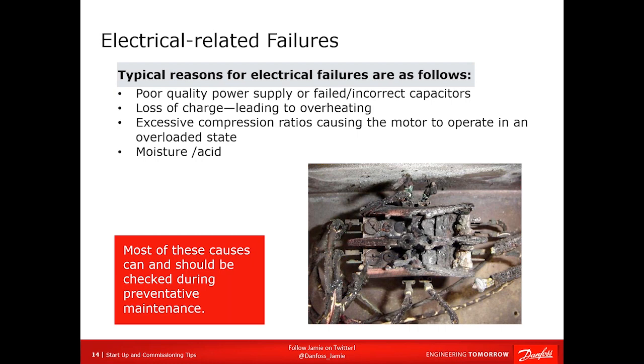All right, excessive compression ratios. We're going to look at the operating profile for these compressors. So if your compressor is operating in a set of conditions it's not designed for, and you overload the motor and not cool it, you're going to have an issue. And this happens, right? Again, that's also a part of loss of charge.